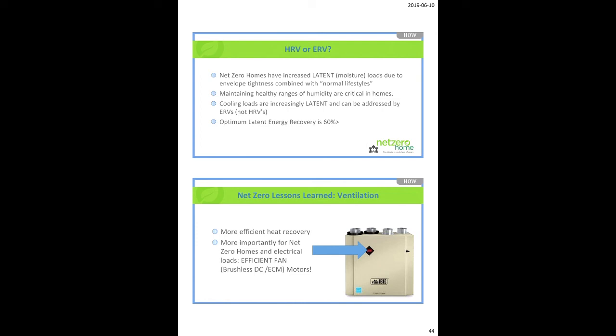And again, keep in mind three types of air you need in the house: ventilation air for breathers, combustion air if there are fuel burning appliances, and makeup air just for your range hoods. We've already spent time on that. People say, well, how do I know if I need makeup air for a range hood? Well, I'm going to tell you, if any of you are doing tight and light houses or net zero homes, you're likely going to need what we call makeup air, or some sort of a hole in the wall that opens up, if you've got a range hood that is over 350 to 400 CFM. Because you've got to remember, with blower door tightness at 1 or less, and you guys are doing 1.5, when we put the door at high speed, the big funny door, at a 50 Pascal pressure difference, we're only depressurizing the house at like 500, 600 CFM. You're going to put a range hood in at 400?